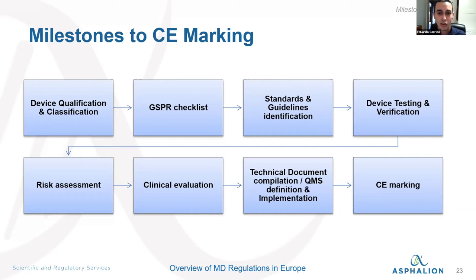This is something that is usually done in parallel. You don't do it step by step, but you take several steps at the same time. You do this risk assessment followed by a clinical evaluation. And then you have to compile all this information in a technical document. You've got to make certain that you have a quality management system in place that is controlling all this documentation. With this, you can undergo a conformity assessment and get your CE marking for your device.